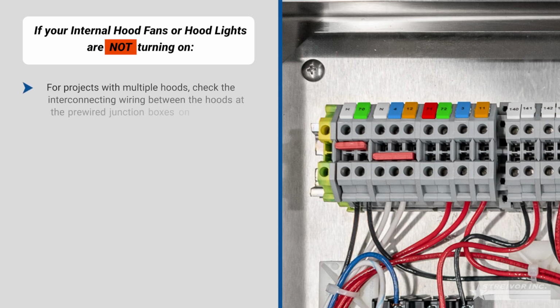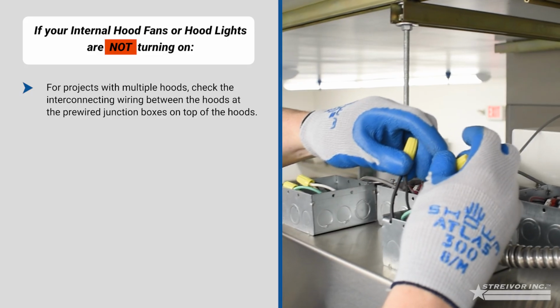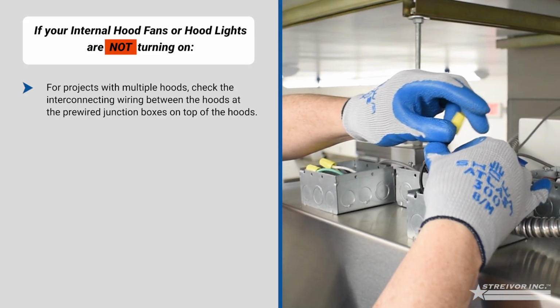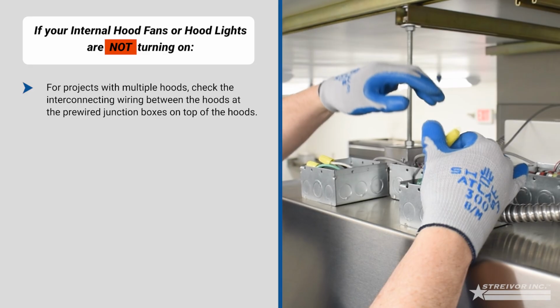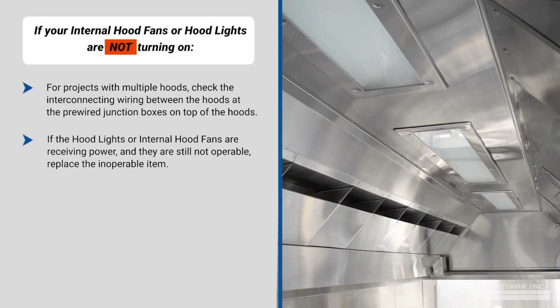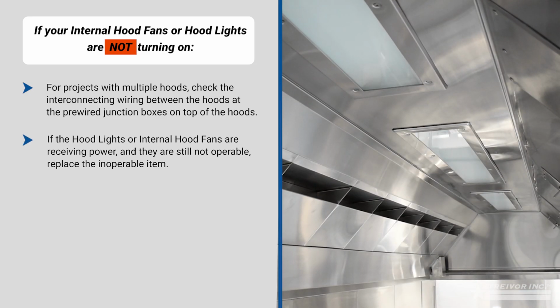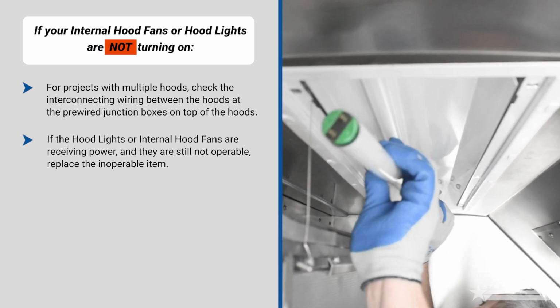For projects with multiple hoods, check the interconnecting wiring between the hoods at the pre-wired junction boxes on top of the hoods. If the hood lights or internal hood fans are receiving power and they are still not operable, replace the inoperable item.